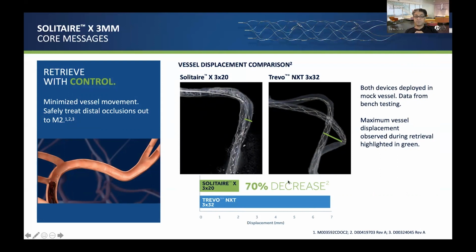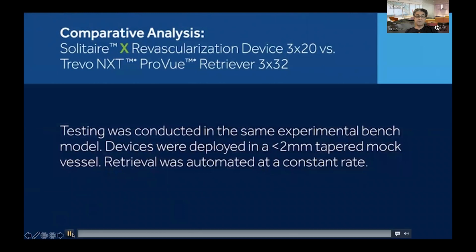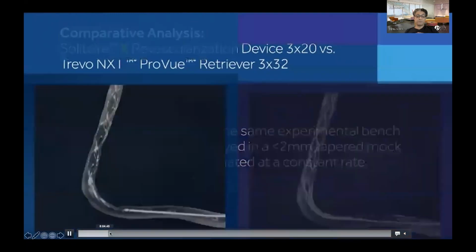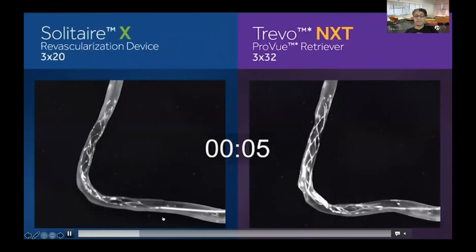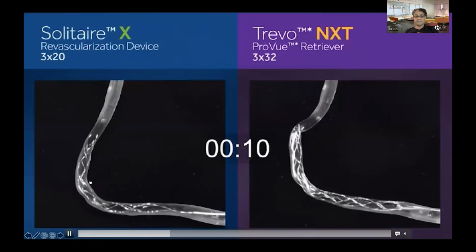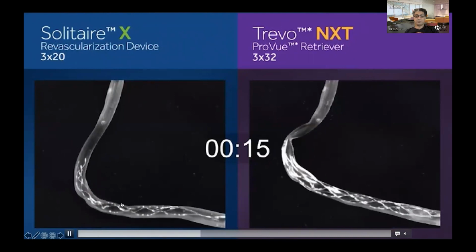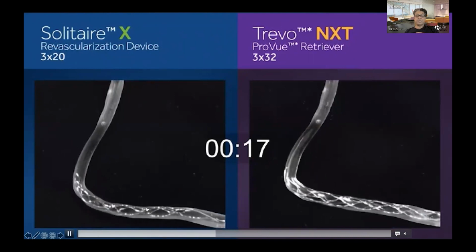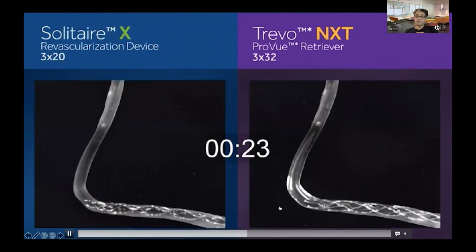And so this is best exemplified through this video, as demonstrated in this little chart here. And I'll turn the music off for reduced dramatic effect. And what you see is the same piece of plastic tubing, and this is the Trevo versus Solitaire. And as the Solitaire is being pulled, it is deforming the plastic tubing a lot less than the Trevo is, which is an innate property of the mechanical features of the device.